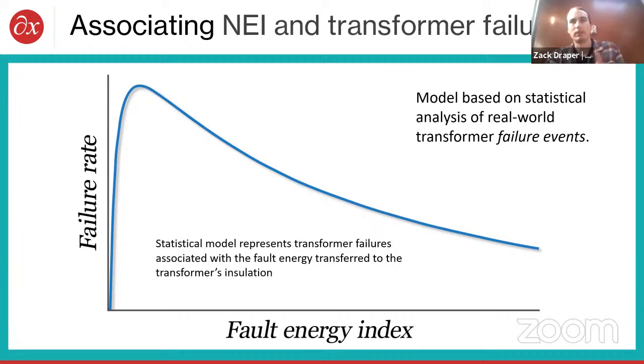What's interesting about this model is that if you look at typical standards that say high gas values represent higher risk, that's the implicit assumption they make. It turns out that's not actually true - the failure rate starts to decline with more gassing. That's something you only learn by a bottom-up approach, by looking at the data and asking what it actually tells you, rather than imposing assumptions from the top down.